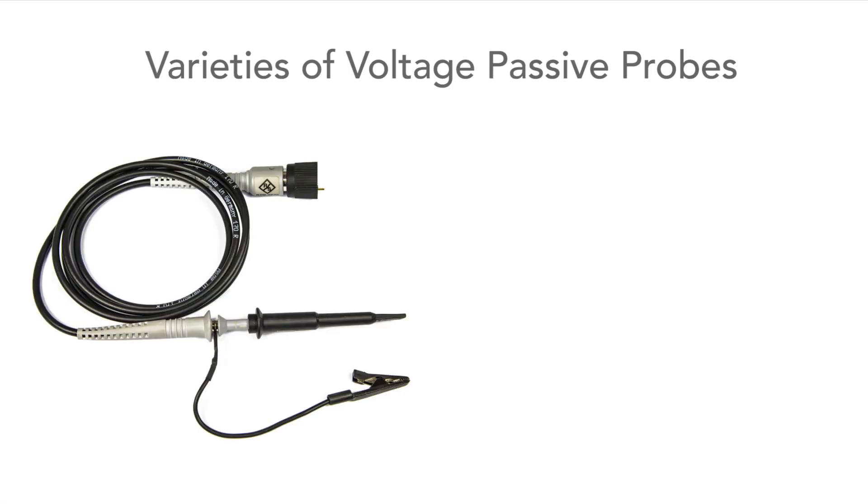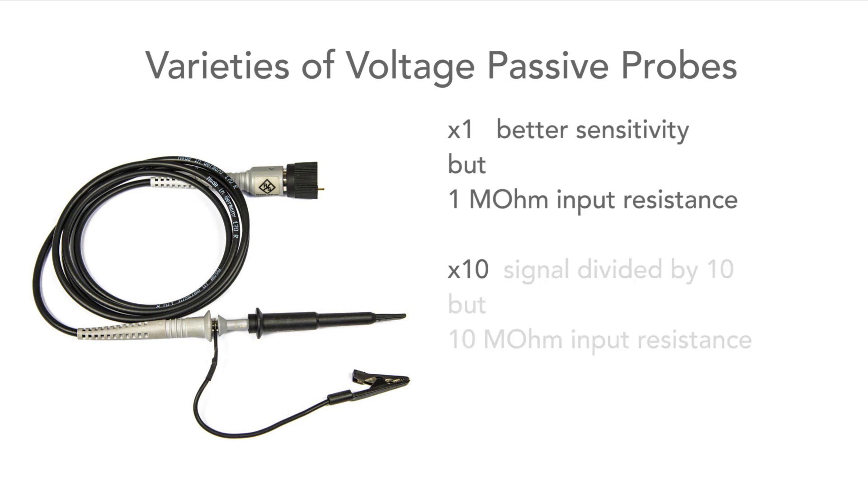This type of probe comes in two main varieties: there's what's called a times one probe and there's also a times ten. The times one gives you better sensitivity but a one megaohm input resistance, or there's the times ten that gives you a ten megaohm input resistance but it reduces the signal by a factor of ten.